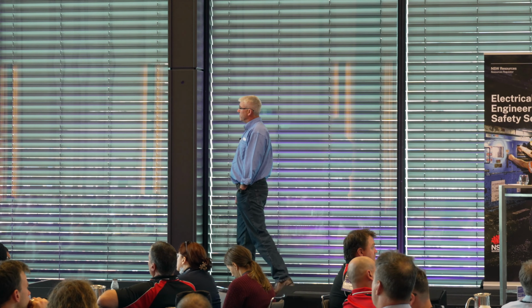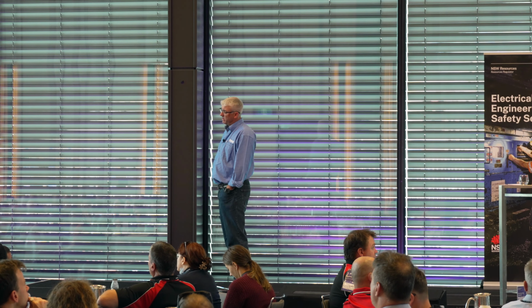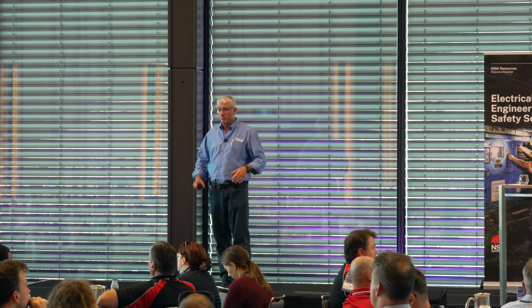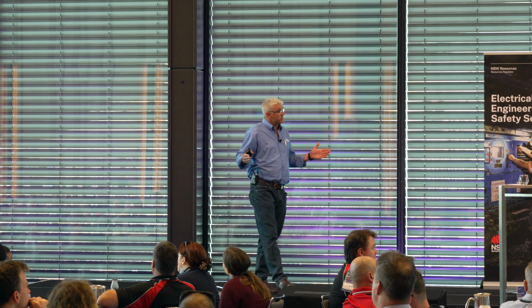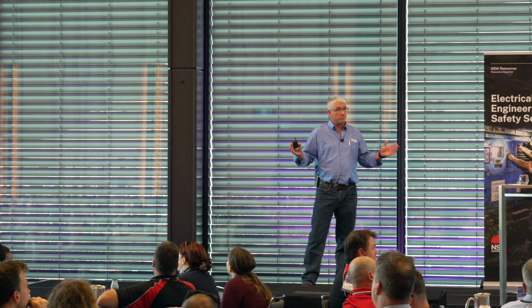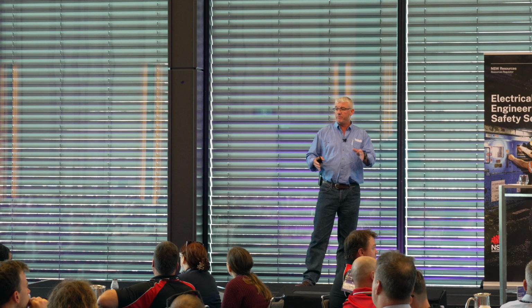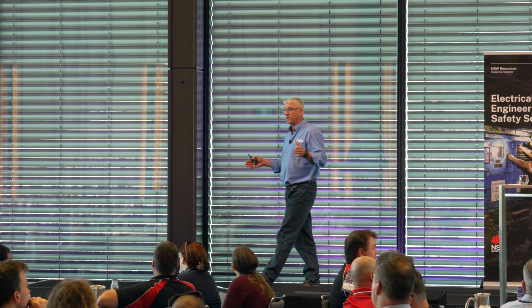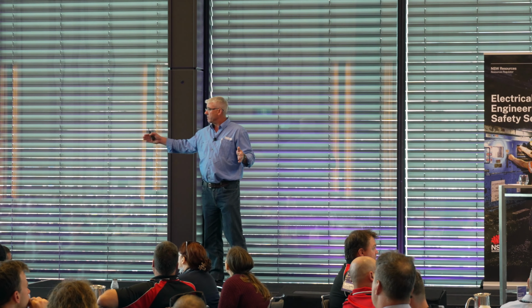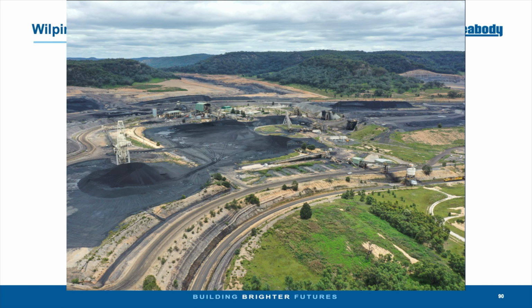We have the original fault level study on site for that area. As the mine's expanded, we've got some pre-start areas where everyone used to start. We've now built new pre-start areas and office buildings in different areas as the mine's spread out. One of those is fed by generators, and another is fed through a 22 kV feeder that comes in.